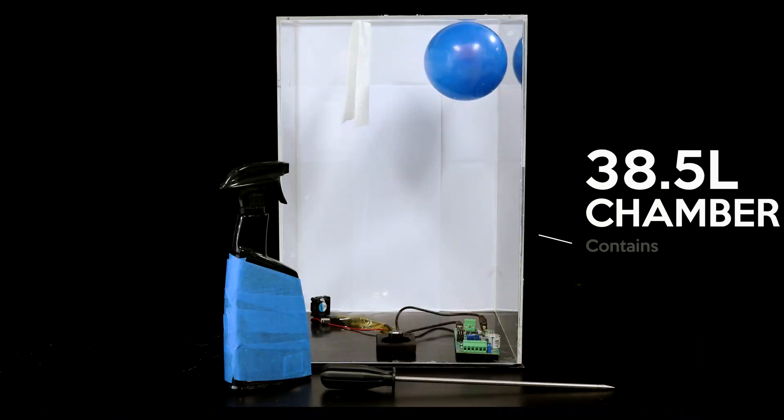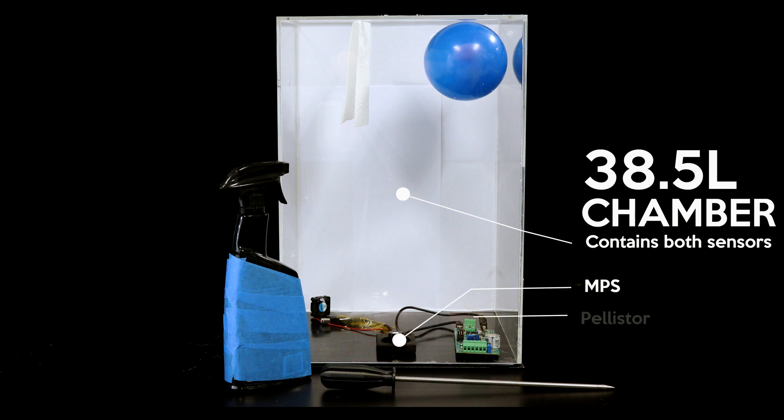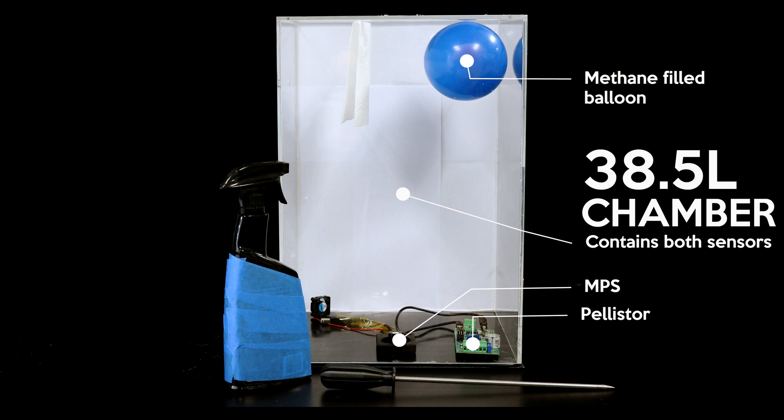This 38 and a half liter chamber contains both sensor types and their evaluation electronics as well as a small fan to mix the gas. The MPS is in the middle front of the chamber and the pellistor is to the right. At the top of the chamber is a balloon filled with methane.